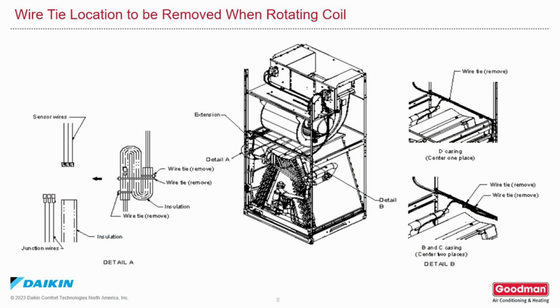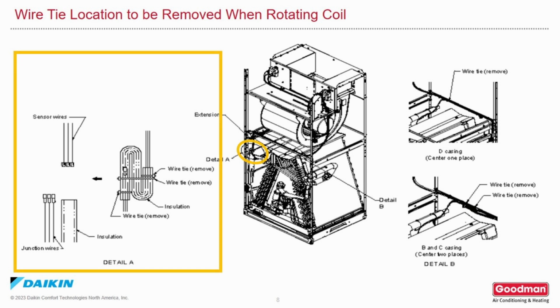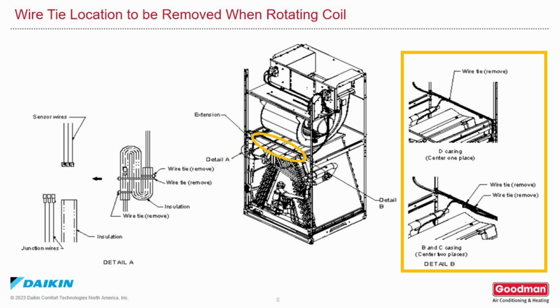Wire tie location to be removed when rotating the coil. Detail A shows the positions of where the wire ties must be removed from the insulation over the junction and sensor wires. Detail B shows where the wire ties must be removed from the support brackets.